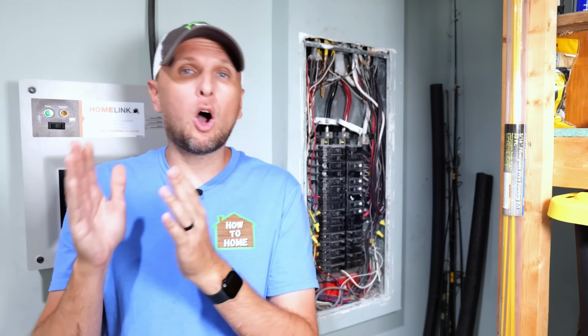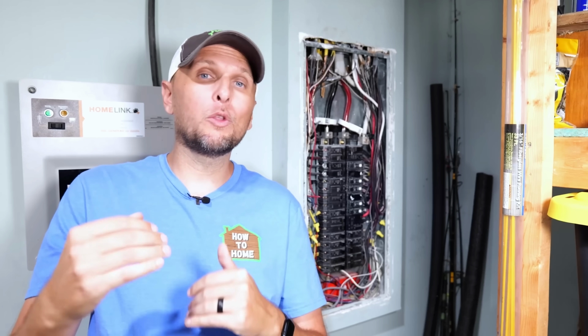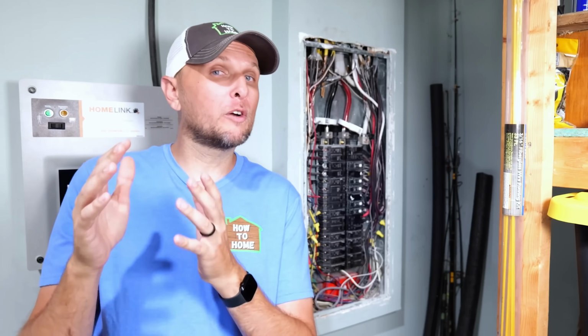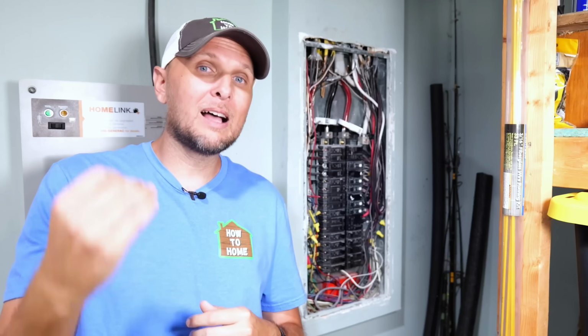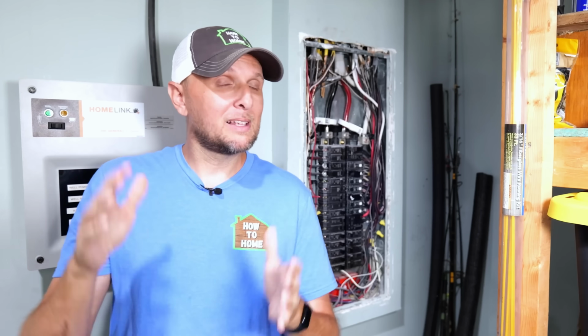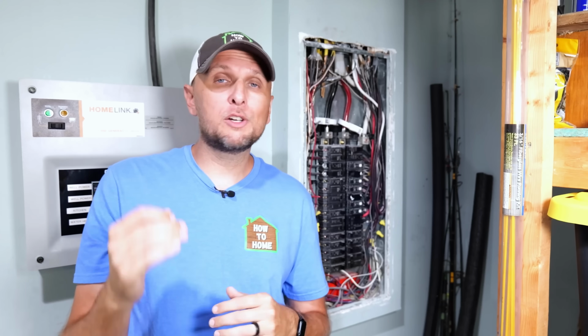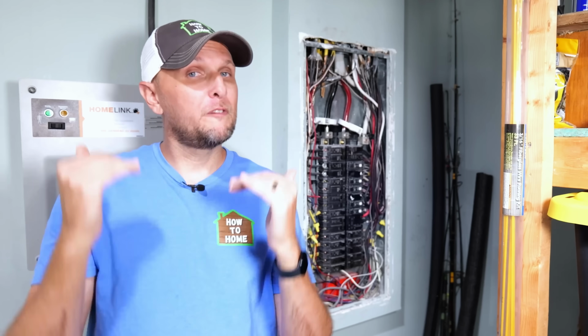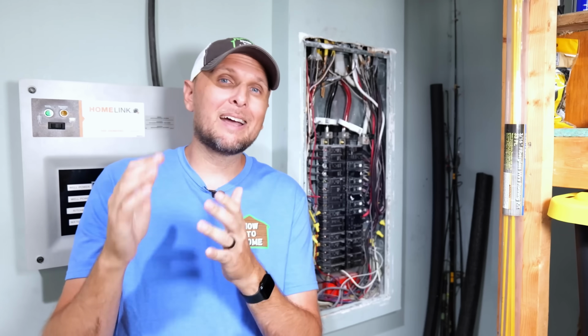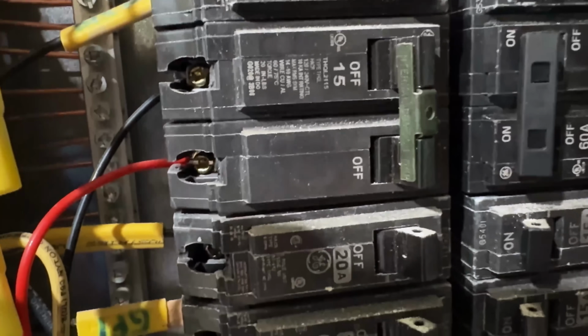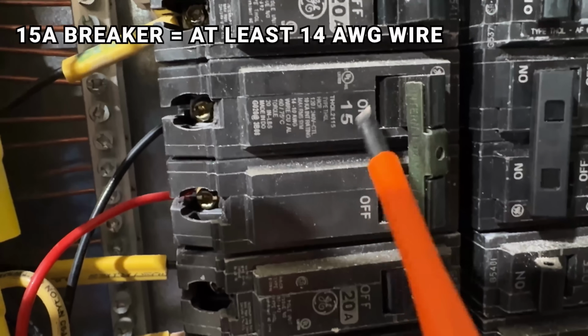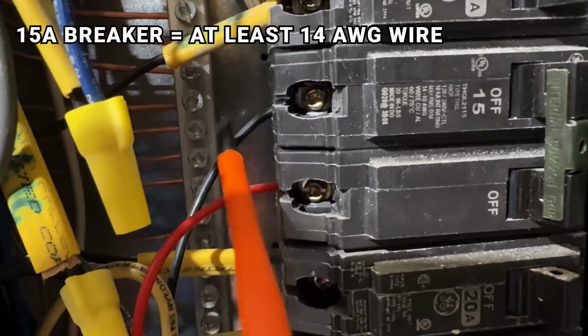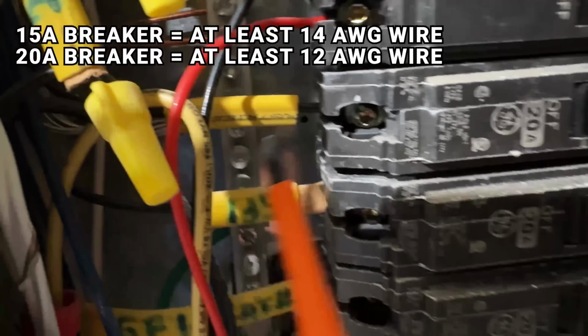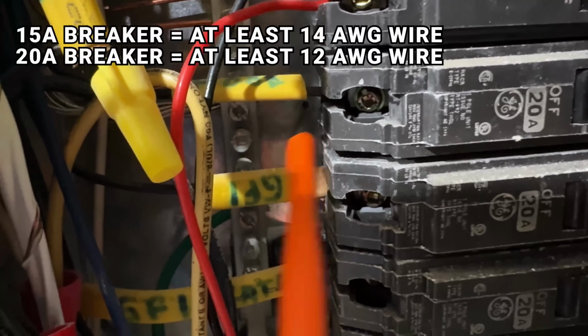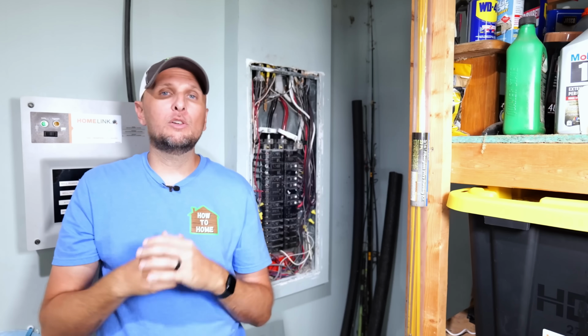But the reason why this is so dangerous is because that number 14 wire on that 20 amp circuit can't handle the potential current, which can lead to overheating or in some cases, and maybe even a lot of cases, an actual fire. Something that's very common that I've seen is melted wires from this exact issue. So the fix for this is also very easy, and that comes down to making sure that you are matching your wire to the breaker. So a 15 amp breaker needs at least 14 gauge wire, and a 20 amp breaker needs at least 12 gauge wire. And of course, the higher up you go, the higher gauge of wire you need.